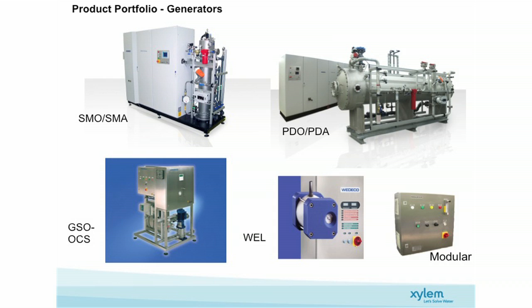So on the larger systems, you can't really use air just because of the volume of gas that you have to process to get the ozone concentration. So our ozone range, we have a full range from a few hundred grams of ozone an hour, all the way up through to our big PDO, which is purpose design systems, which we are now producing over 250 kilograms an hour of ozone in a single unit. So the world's largest ozone generators. That's what they look like. Effectively, it's a big shell and tube heat exchanger. We'll go into a bit more detail of the workings now.